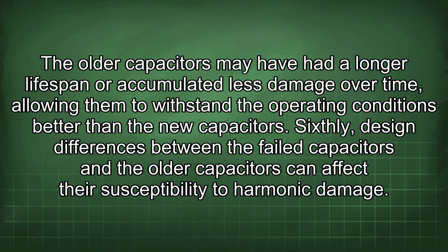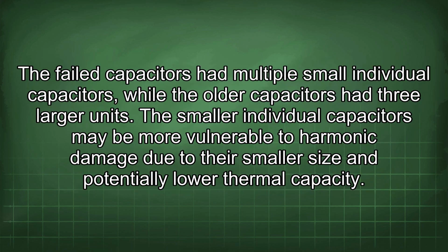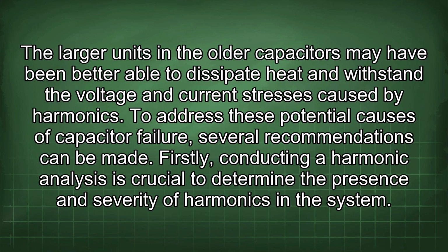Sixthly, design differences between the failed capacitors and the older capacitors can affect their susceptibility to harmonic damage. The failed capacitors had multiple small individual capacitors, while the older capacitors had 3 larger units. The smaller individual capacitors may be more vulnerable to harmonic damage due to their smaller size and potentially low thermal capacity. The larger units in the older capacitors may have been better able to dissipate heat and withstand the voltage and current stresses caused by harmonics. To address these potential causes of capacitor failure, several recommendations can be made.